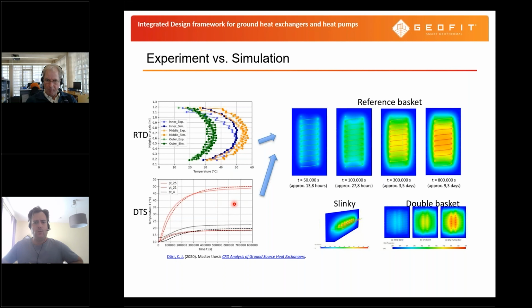We have a rapid increase with passing time, which can be observed in the early transient stage. This is this part, while near steady state conditions are clearly visible after probably 9 days. Initially, the temperature difference at the discussed PT1000 sensor positions seemed quite large. However, at time zero, at the initial conditions, a distinct offset at all three sensor positions can be observed. So this is a calibration issue, more or less.